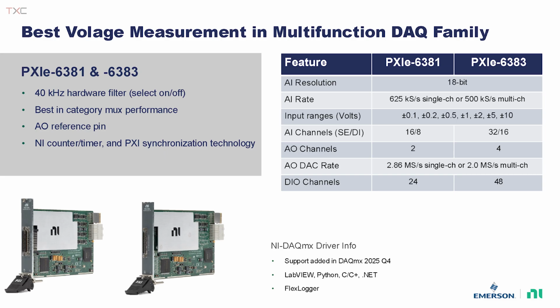It's not just that, we also look at all the gain settings. You can set the range on this from 10 volts all the way down to plus or minus 100 millivolts, with 5 spots in between, so you can really dial in to minimize the noise impact on the measurement.